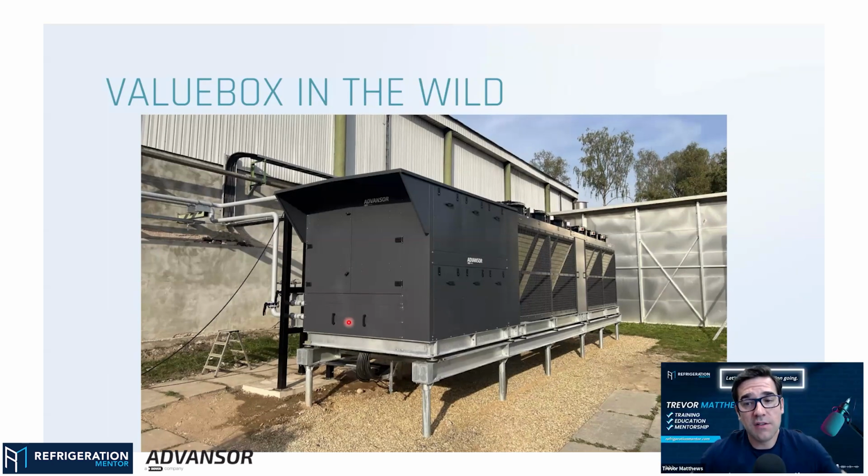Yeah. So this is different than if you're working on, say, refrigeration and supermarket systems, unless you do secondary systems like secondary pump systems, because now we're dealing with flow. This is not anything to do with the manufacturer of the heat pump. Now we're dealing with flow. So there are circulation pumps or process pumps, whatever you want to call them. And if those process pumps are not supplying the right flow, that is going to change the whole system dynamics. And you've got to get into something like pump curves and things like that. So is that some of the stuff that you're talking about, Erik, for the contractor?